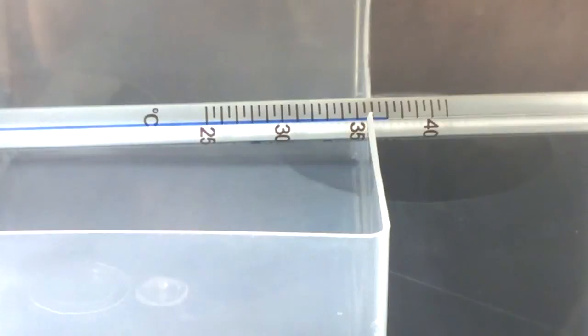If we look now at the thermometer, the glass thermometer, again we can see that temperature is rising. It is now at 37 degrees. It's just got to 37 there as it hits that longer line, and it's keeping going up. So on the glass thermometer it's a little bit harder to get within 0.2, but between that longer line that we can see, we're at 37, and the next long line is 38. So the little middle line between those two is 37.5.